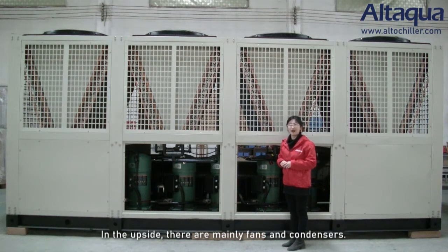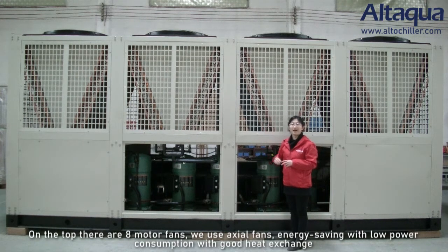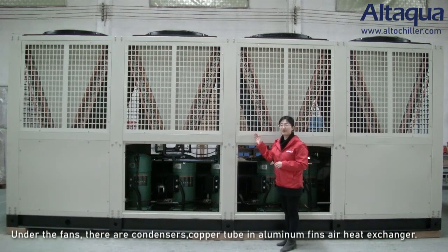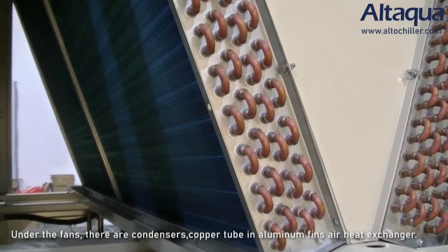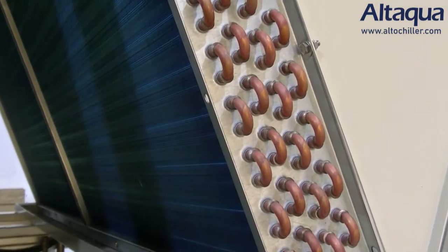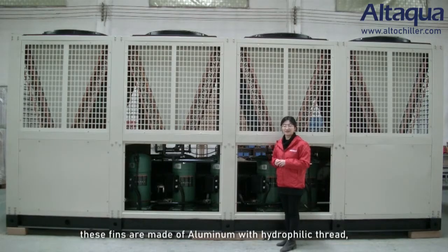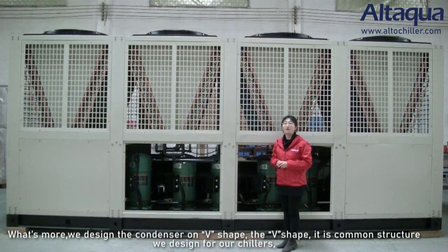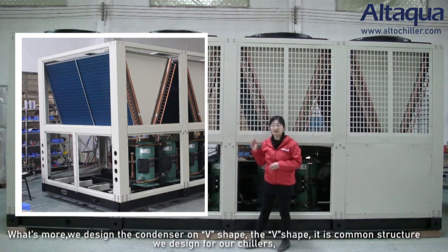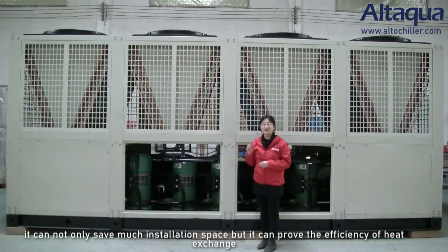On the upside, there are fans and condensers. On the top, there are 8 motor fans. We use axial fans. They are energy saving with low power consumption, but with good heat exchange. Under the fans, there are condensers, copper tube in aluminum fins, air heat exchangers. These fins are made of aluminum hydrophilic foil. What's more, we designed the condenser in a V shape. The V shape is a common structure we designed for our chillers. It can not only save much installation space, but also improve the efficiency of heat exchange.